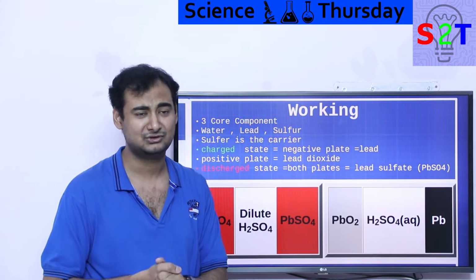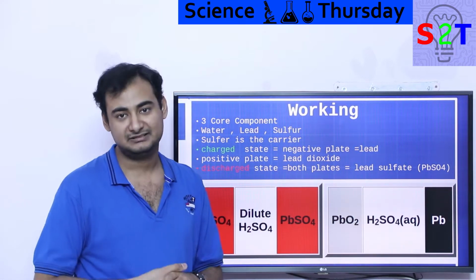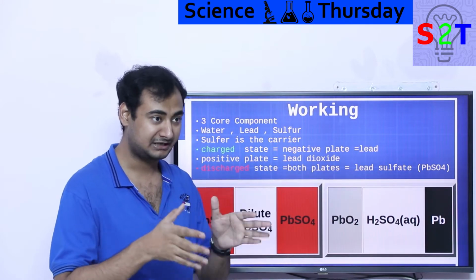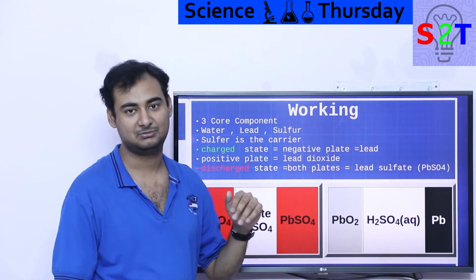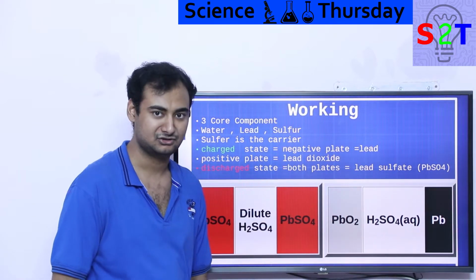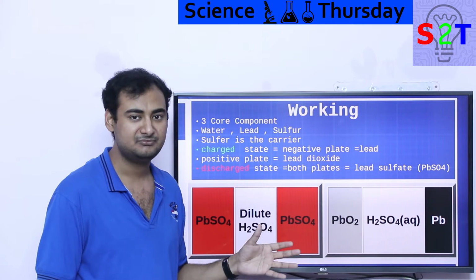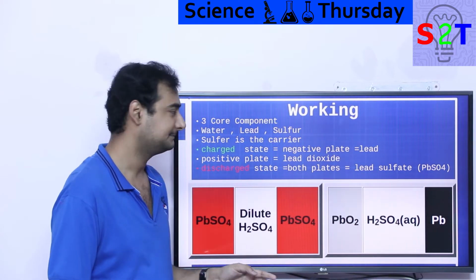Now they do not do that anymore because A, we are very good with it, we have 100 years of experience handling it, and B, the hydrogen outflow is not too much, and the primary reaction itself is not just mass producing hydrogen. Otherwise, these batteries would turn into something where you just have tanks of water in your car, but otherwise the battery will not work. So hydrogen outgassing is a serious threat, it does happen, it does set things on fire, but it's very well managed, and unless you are ludicrously stupid or ludicrously careless, it will never happen.